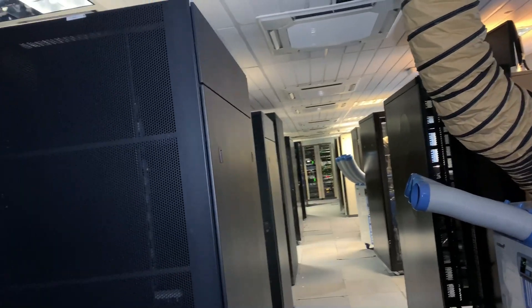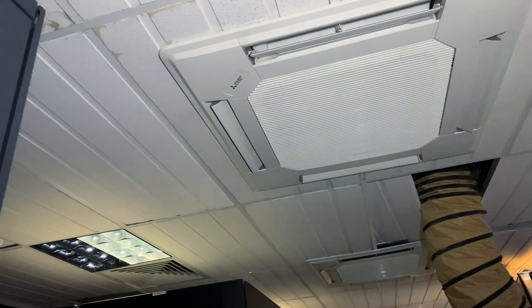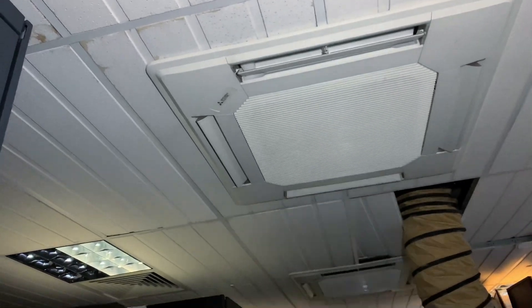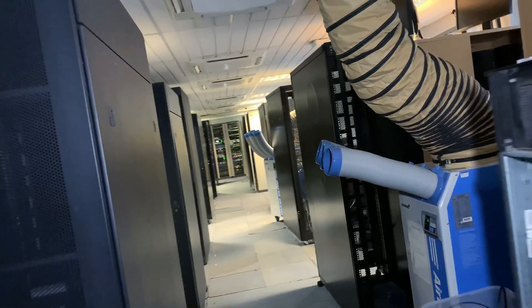Obviously we're in a server room — there's a lot of kit in here, probably too much heat load for the equipment we've got, so it does have an effect when we turn one of these off. They're twin splits, so when I turn this off another one's going to go off as well. You'll see they've got a few temporary units rigged up down there.